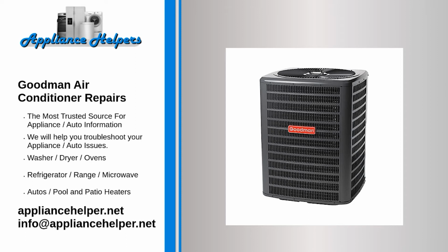Goodman central air conditioner is noisy or loud. The condenser fan motor has bearings that can wear out over time. When the bearings are worn out, they make loud noise. To check the bearings, try rotating the condenser fan motor by hand. If the motor does not turn smoothly, replace it.